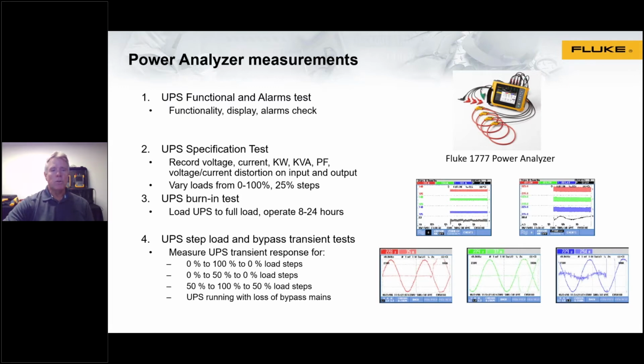So test number 2, it's called a UPS specification test. What the analyzer would be doing, and actually for this test, you would need to have 2 analyzers, one on the input side and one on the output side, and then to be able to compare readings. So what you'd be doing would be recording voltages, all 3 phases of voltage, current, real power or kW, apparent power, kVA, power factor, and then also looking at voltage and current distortion on both the input and the output.